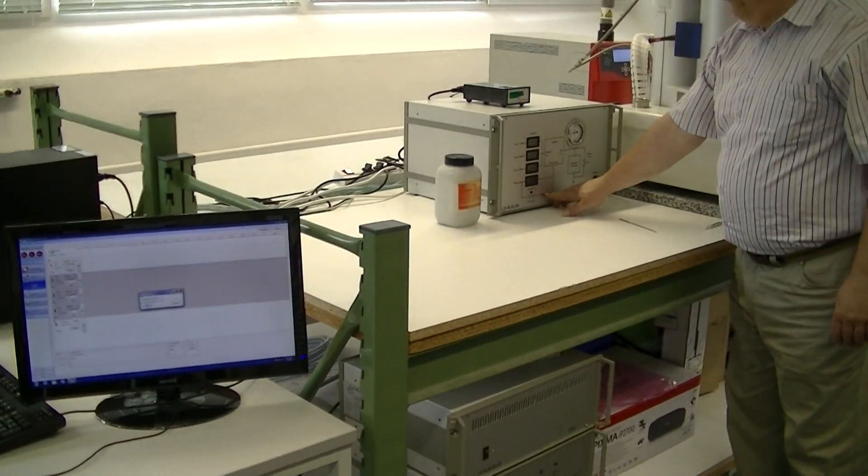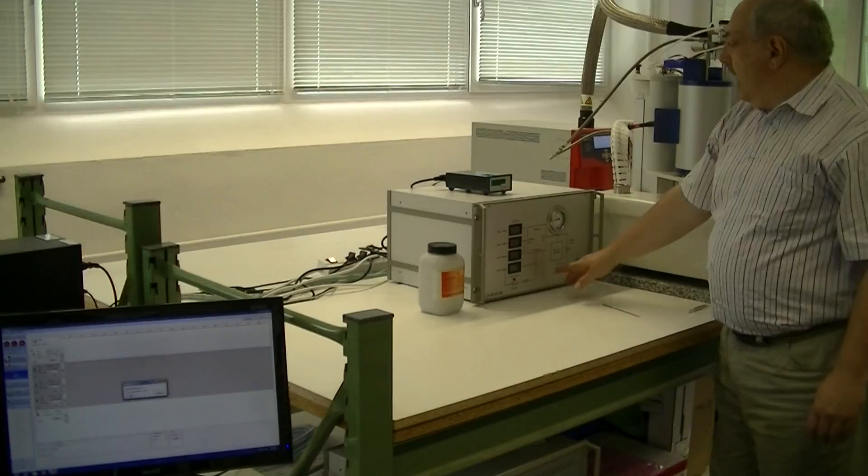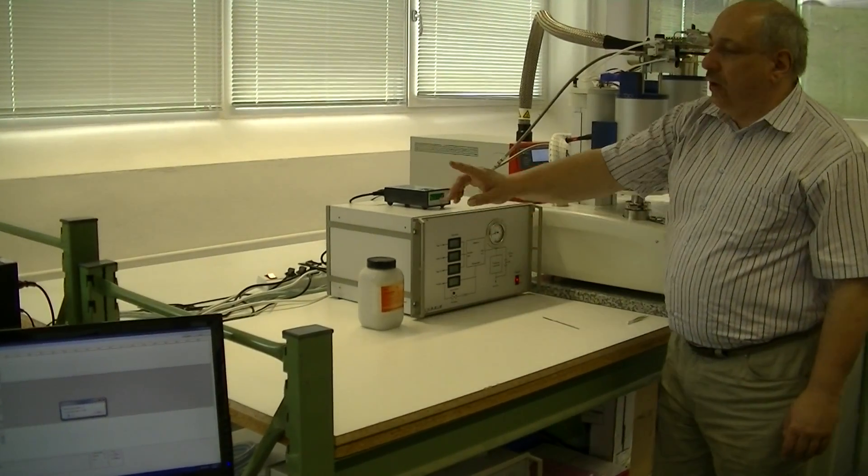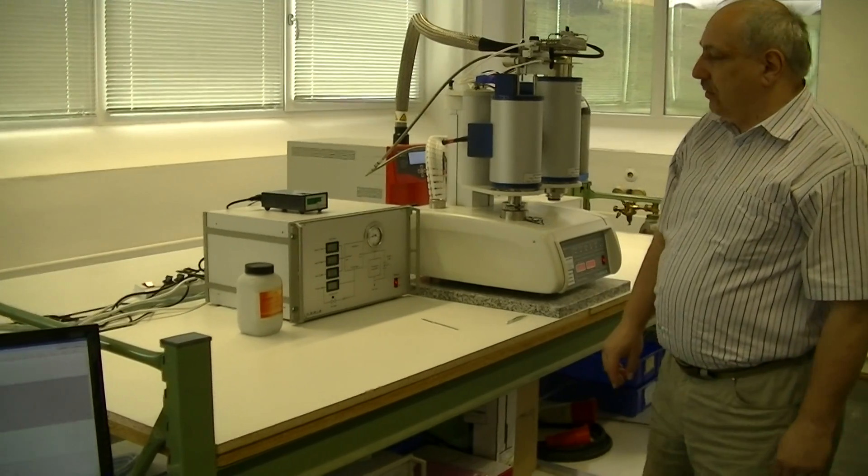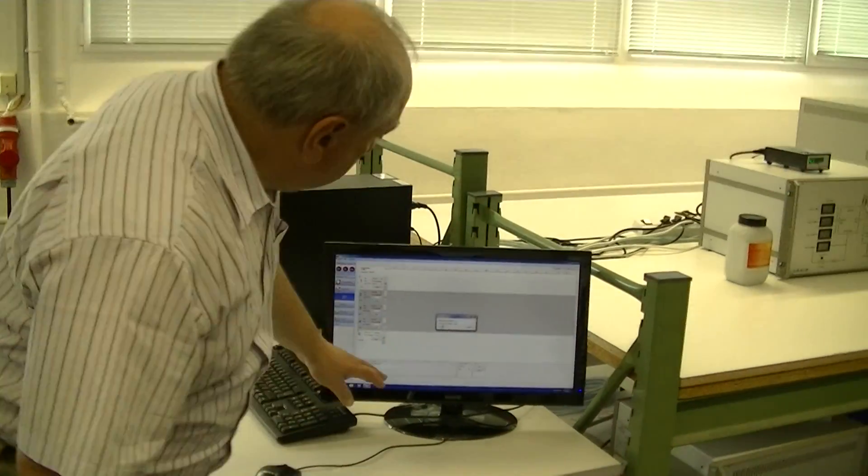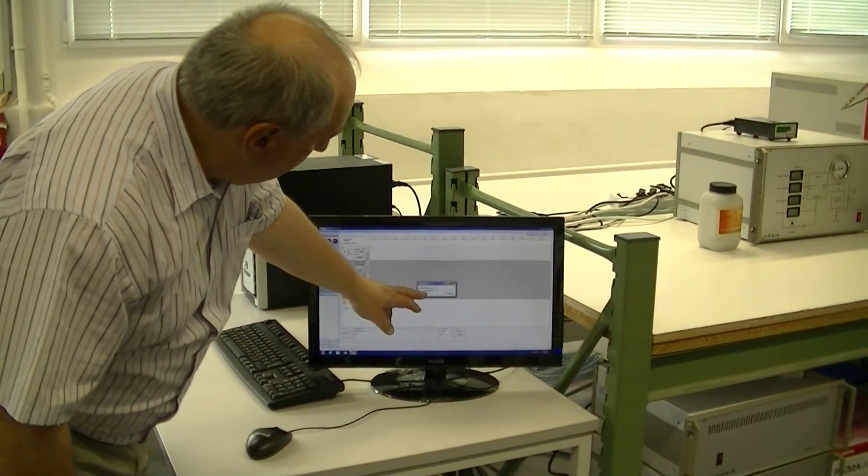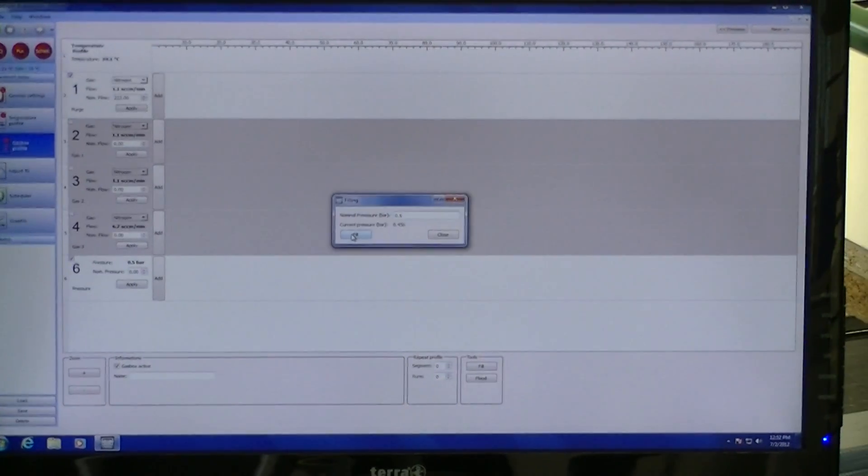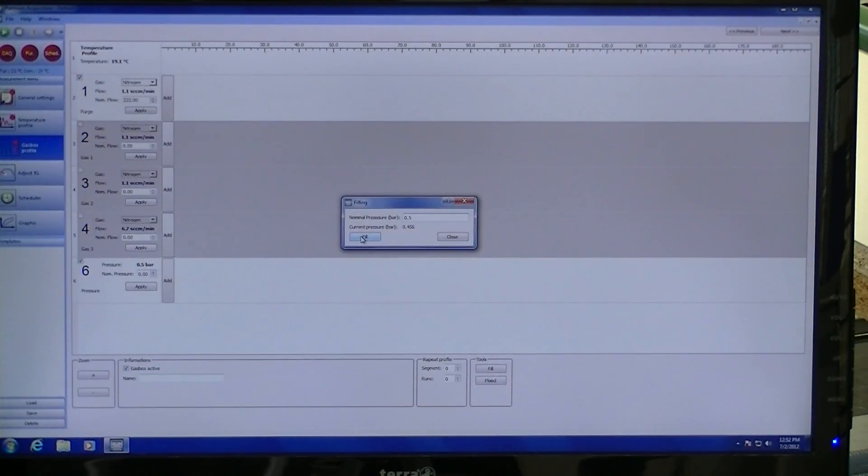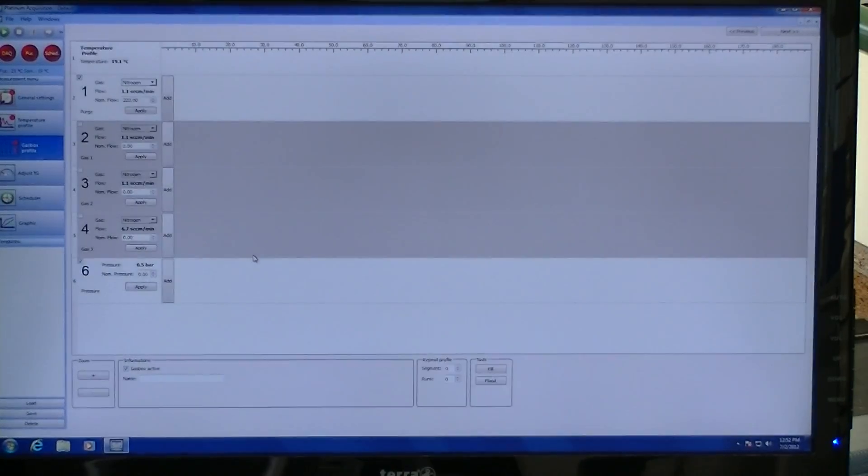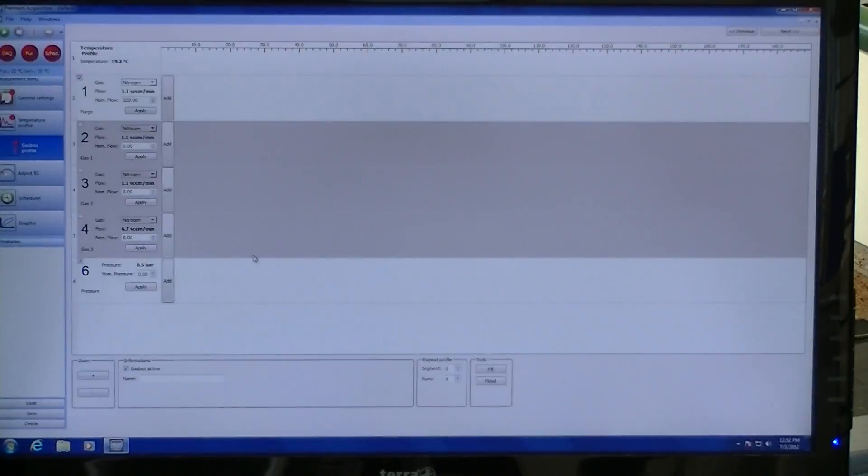The inlet purge gas valve is now open. It fills the gas into the chamber slowly. And the pressure will be indicated here or also in the software from the pressure controller system. We adjusted about 0.5 bar and we are seeing in the moment the current pressure inside the system is nearly 0.5 bar overpressure. So the system is full and inlet valve will be closed automatically when the pressure is reached. You can adjust any pressure now between 0 and 7 bar.